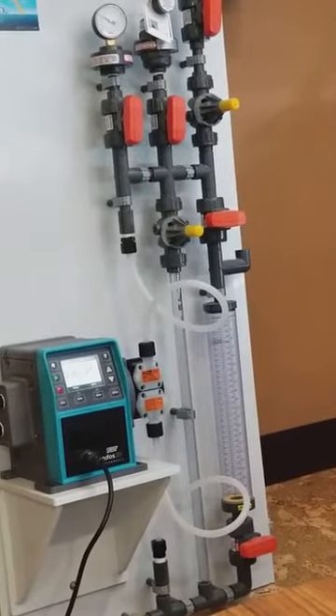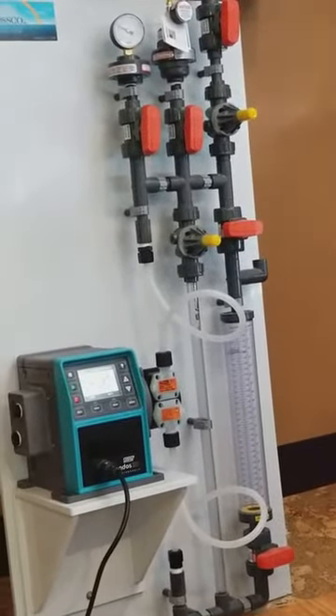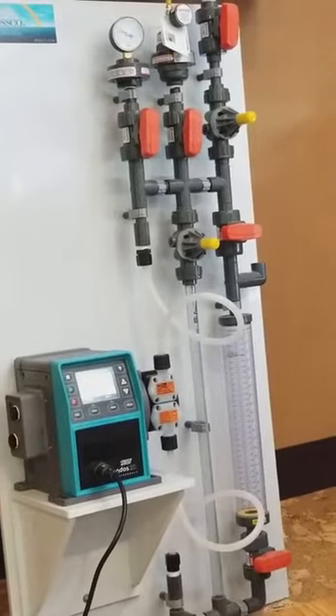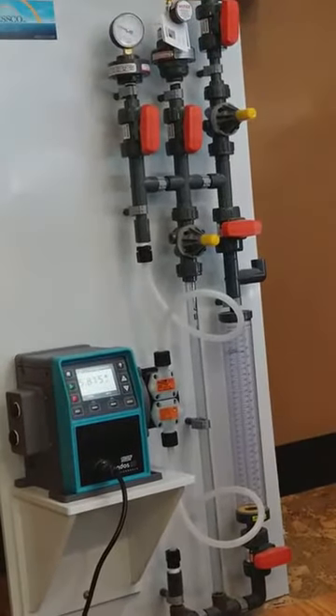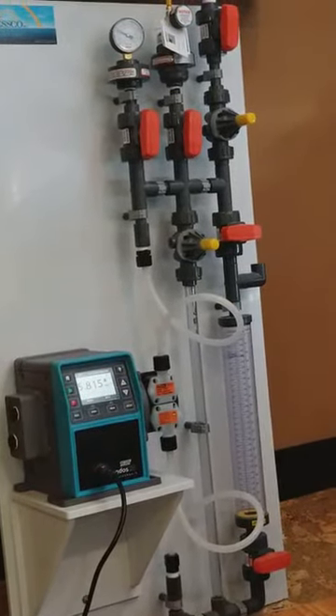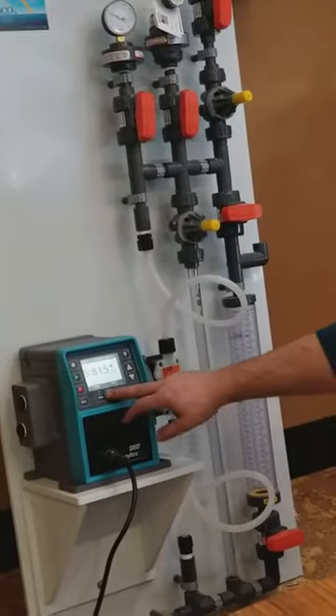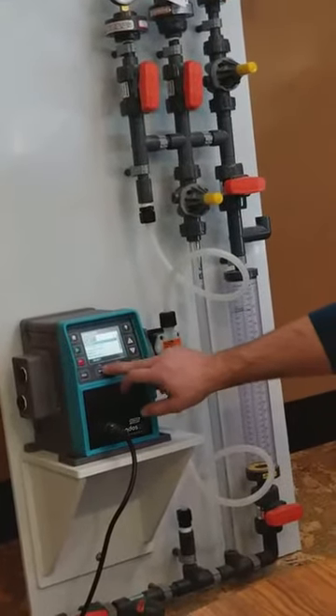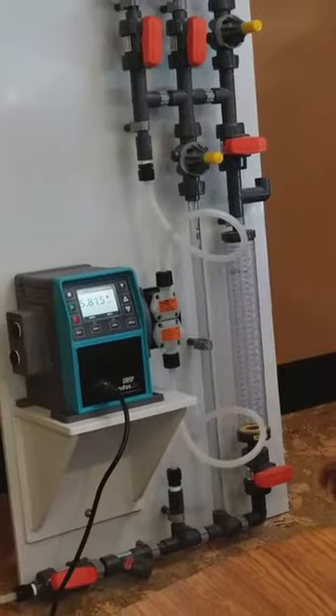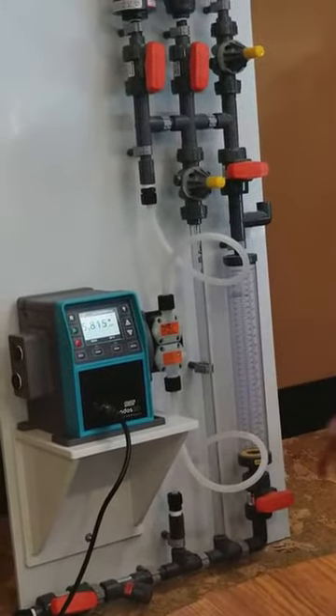Alright, this video is going to be on calibrating a Watson Marlow pump. Most of the Watson Marlows are now operating all the exact same type of system of how to do a calibration. So first things first, we're going to want to make sure that our pump is in manual mode. And the first thing we're going to do is fill our calibration column.